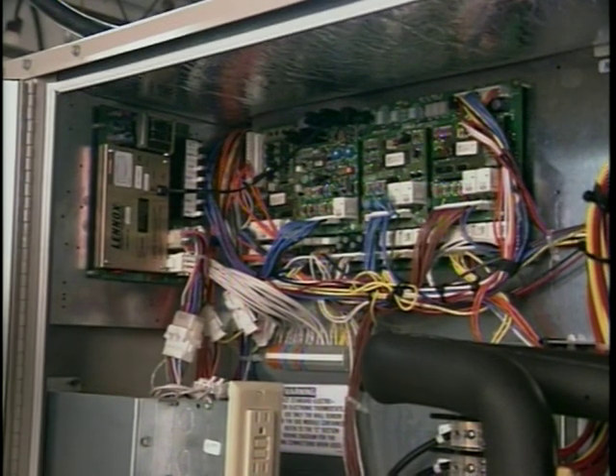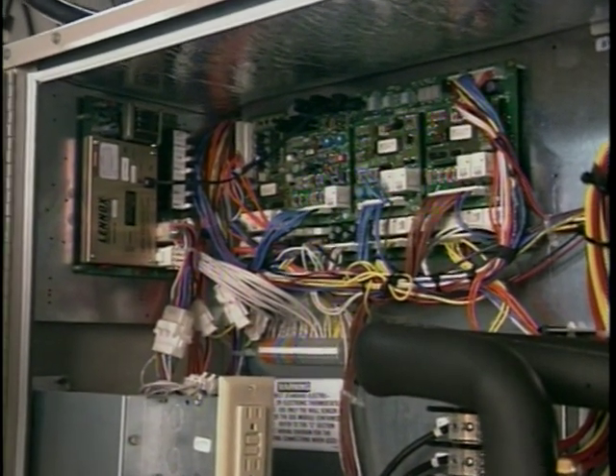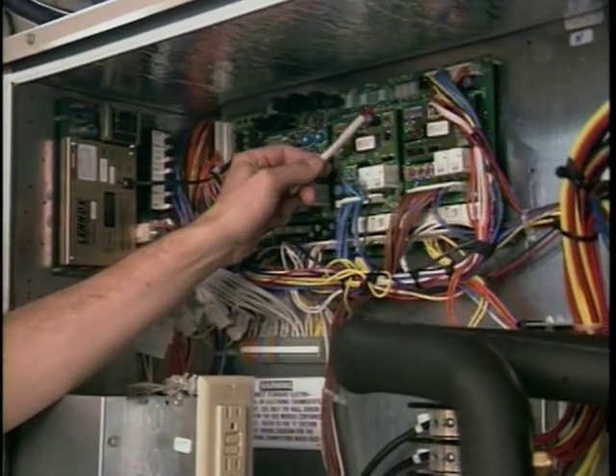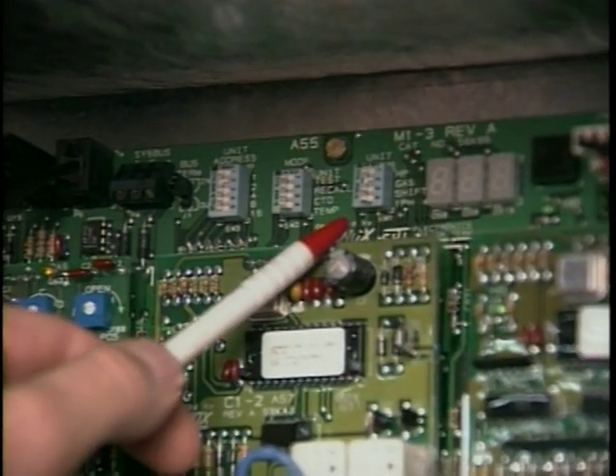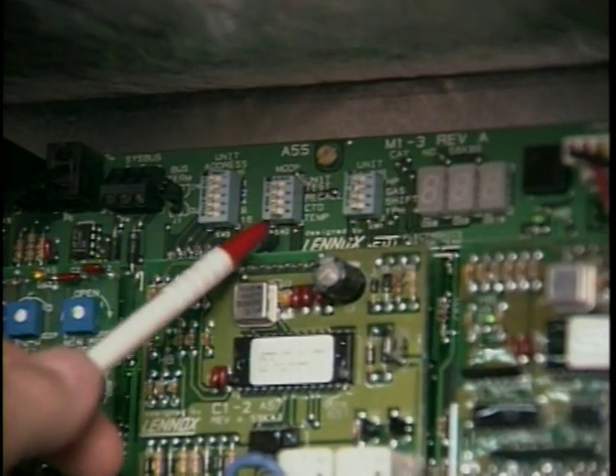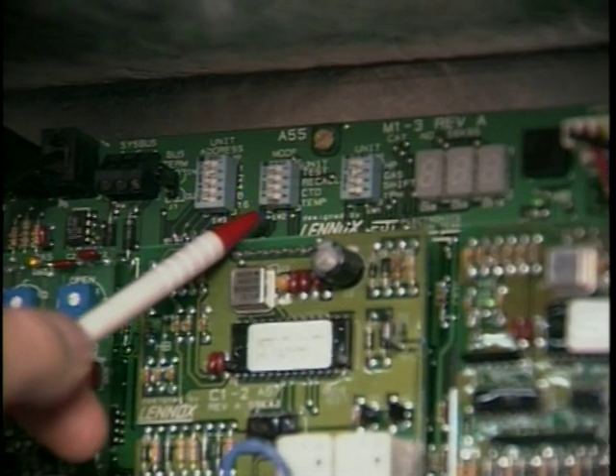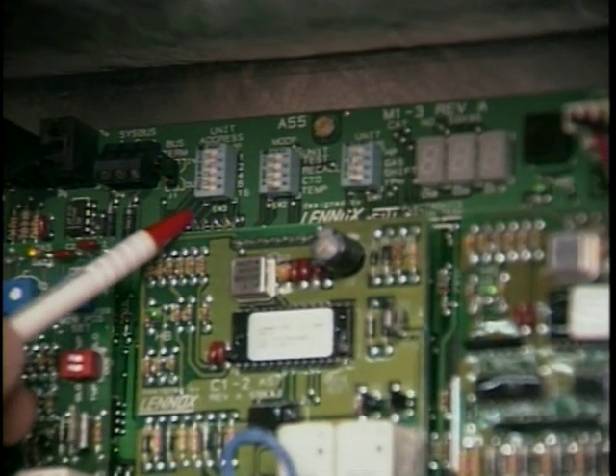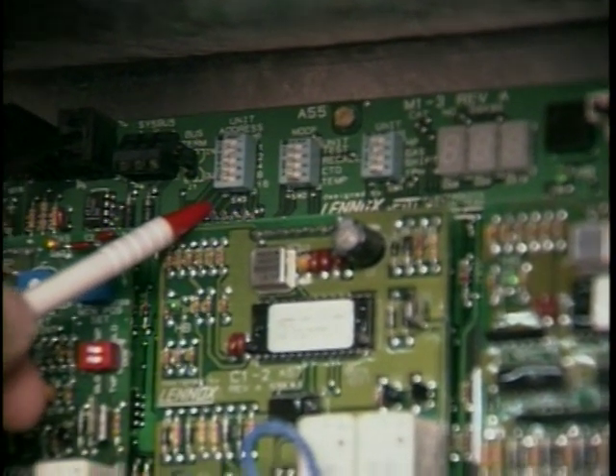Check that the settings on SW1 agree with the type of unit you are checking. Refer to the EOC instructions and the IMC manual for correct settings. Check that on SW2 all switches are off. Check that on SW3 the second switch is on and all others are off.